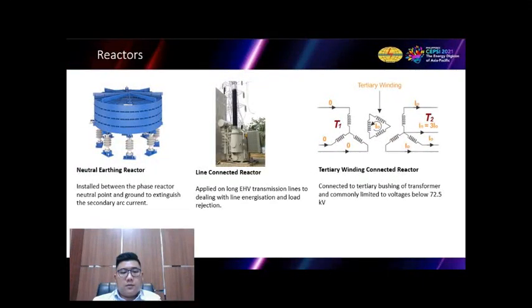Well, in this slide, we are talking about the reactor. Firstly, is neutral grounding reactor. Neutral grounding reactor is installed between the shunt reactor neutral coil and the ground to extinguish the secondary arc current. Secondly, is line connected reactor, applied on long EHV transmission line to deal with the line energization and load rejection.